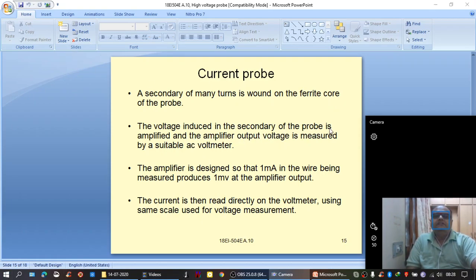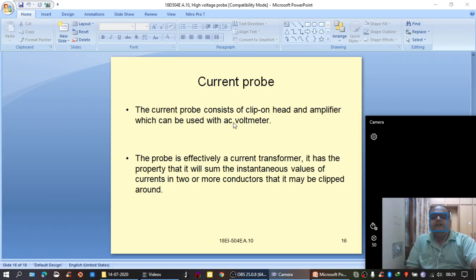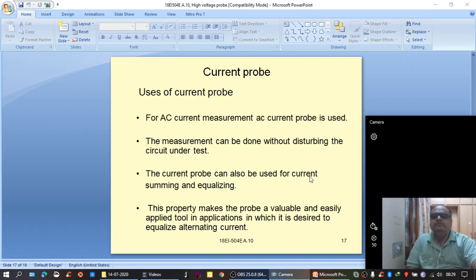The voltage induced in the secondary of the probe is amplified, and the amplifier output is measured by a suitable AC voltmeter. The amplifier is designed so that 1 milliampere in the wire being measured produces 1 millivolt at the amplifier output. The current is then read directly on the voltmeter using the same scale used for voltage measurement. Instead of 1 millivolt, we will read it as 1 milliamp. The current probe consists of a clip-on head and amplifier which can be used with an AC voltmeter. The probe is effectively a current transformer. Okay, all this we have seen.